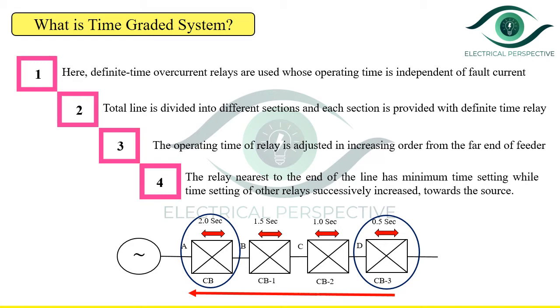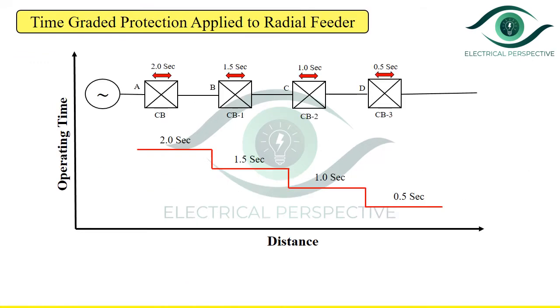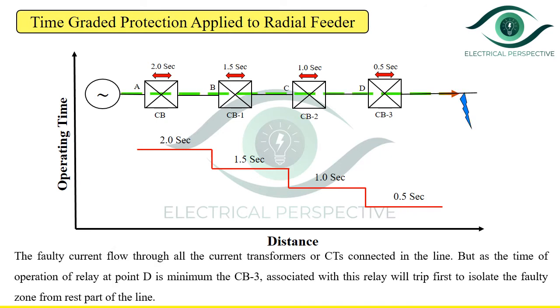The minimum time interval allowed between two adjacent circuit breakers depends on its own clearance time plus a small time for safety margin. In the example of the time graded system applied to the radial feeder, if a fault occurs nearer to the load end, the fault current flows through all the circuit breakers and CTs connected in the line. But since the operating time of the relay at point D is minimum, circuit breaker CB3 associated with this relay will trip first to isolate the faulty zone from the rest of the system.